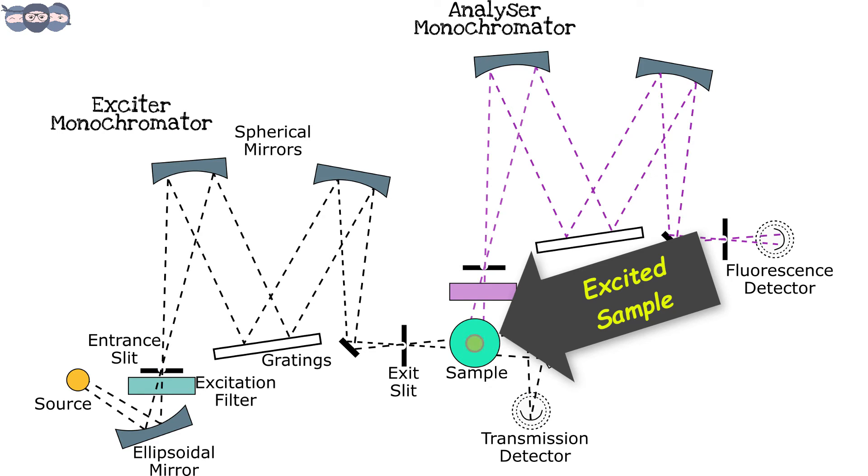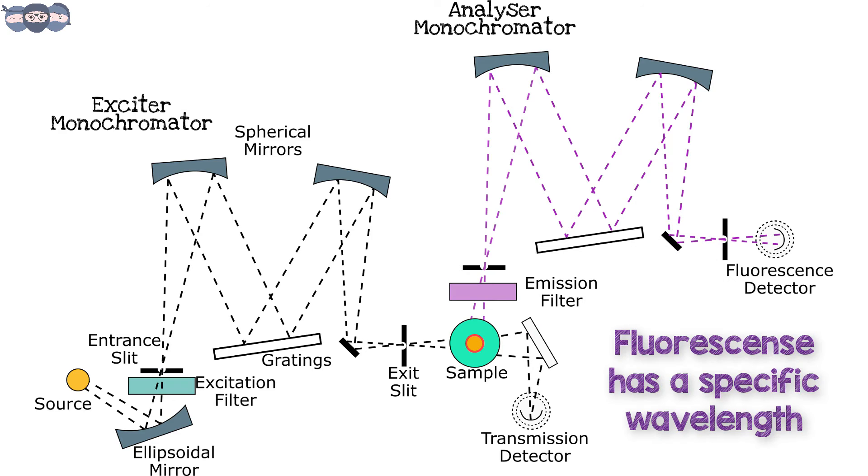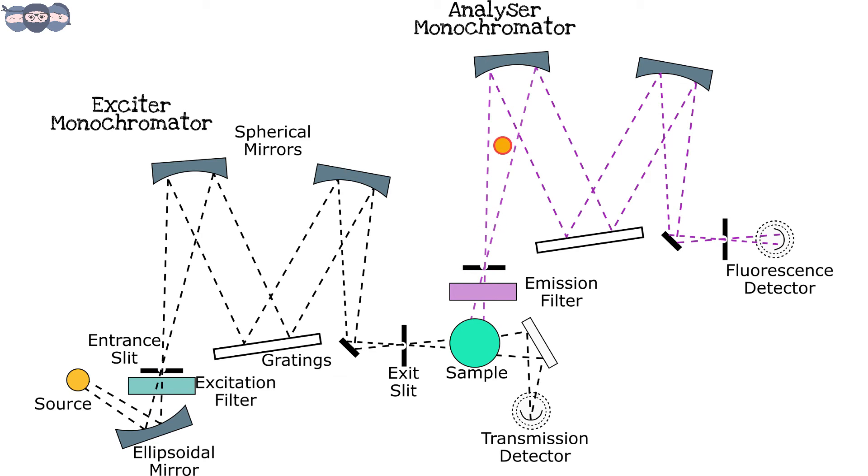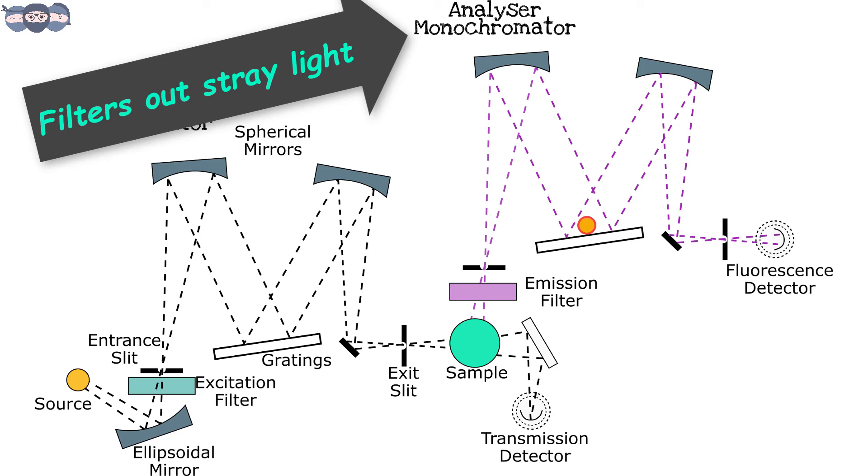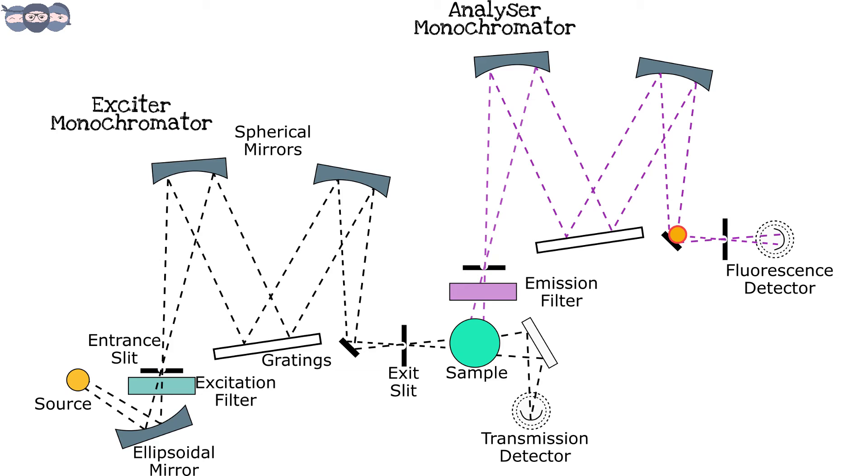The sample gets excited by the incident radiation. The phenomenon of fluorescence takes place and fluorescence of a particular wavelength is emitted by the sample. This emitted radiation is made to pass through the analyzer monochromator which filters out any stray light mixed with fluorescent radiations. Once the fluorescence exits the analyzer monochromator, its intensity is measured by the detector which is generally a PMT.